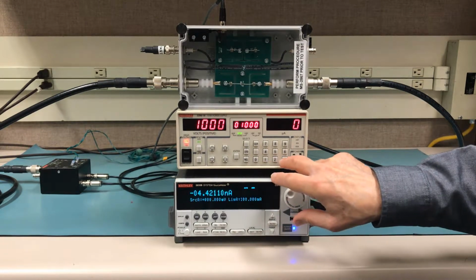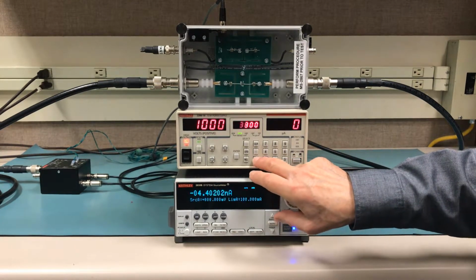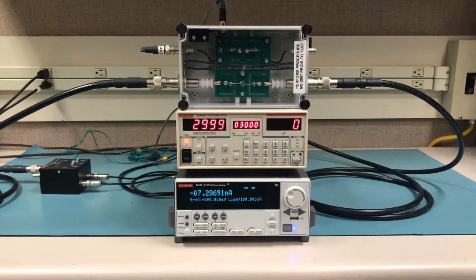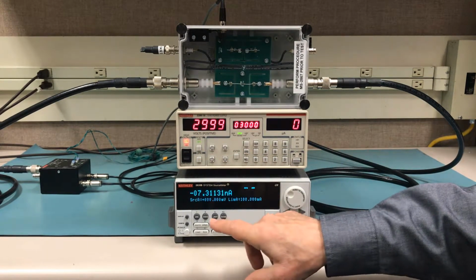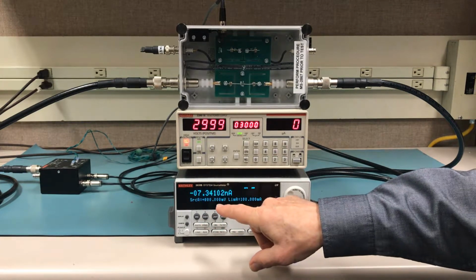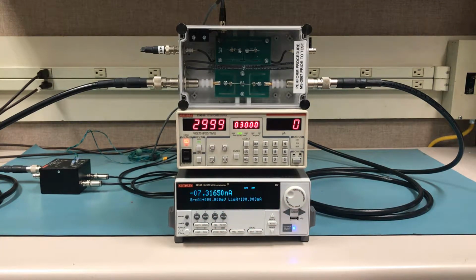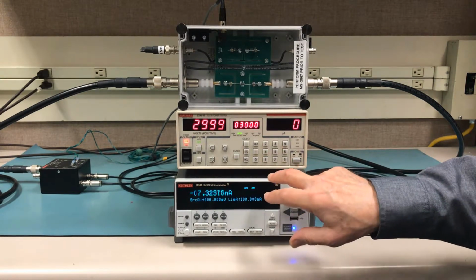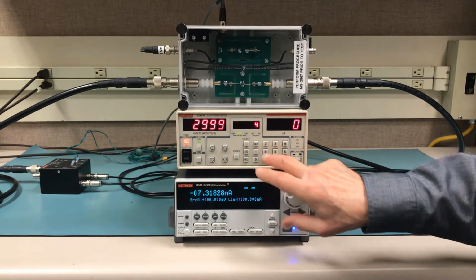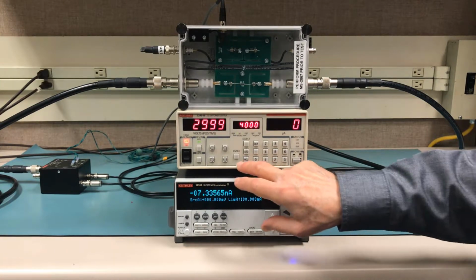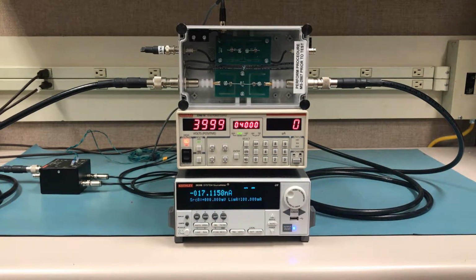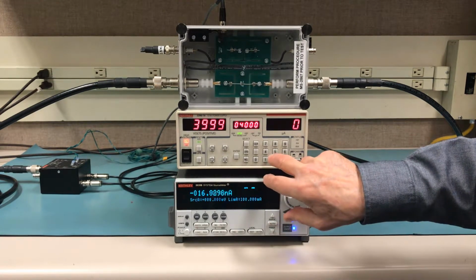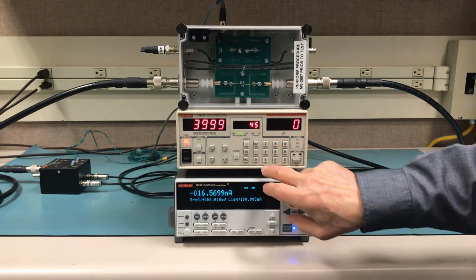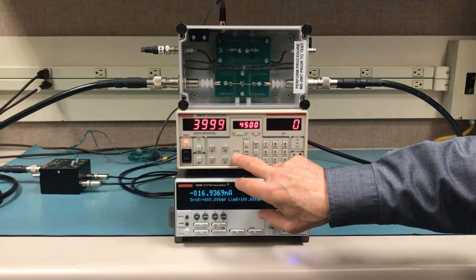I'll go to 3,000 volts. And our diode is still very good with back bias voltage leakage of only 7 nanoamps. It's a 4 kilovolt diode, so let's run it up to 4,000 volts. And it's still meeting its specification, still in the nanoamp range. Well, let's challenge it and let's go up to 4,500. It's greater than 10% above its rating.